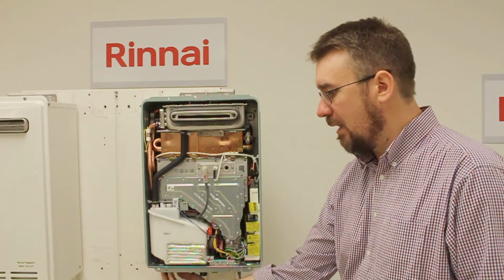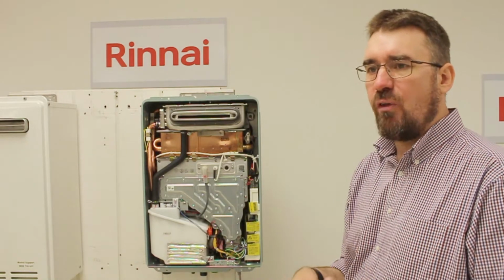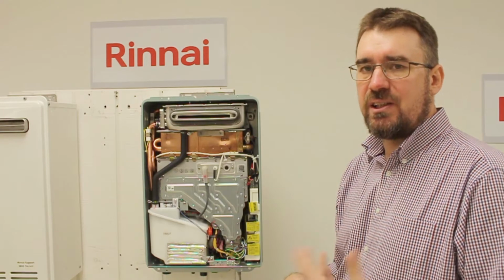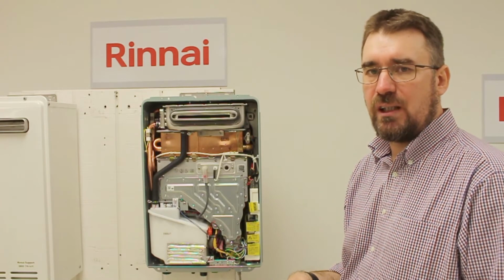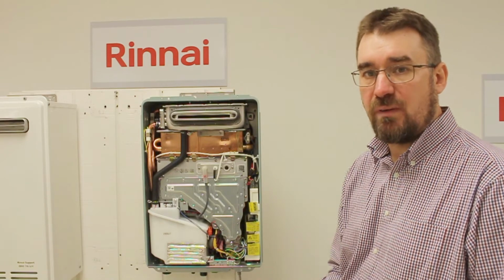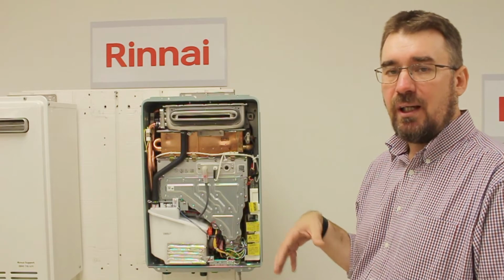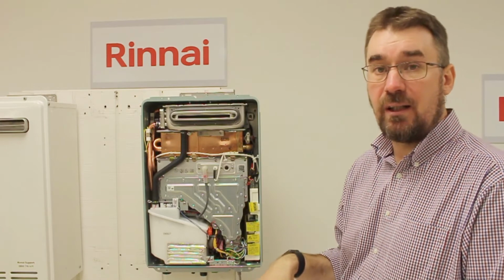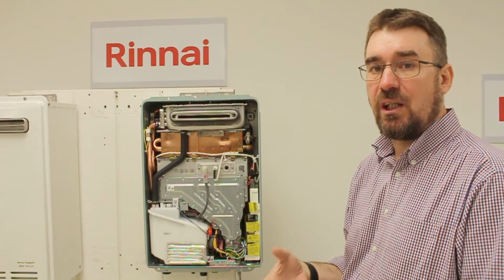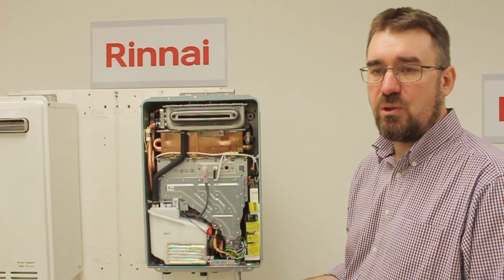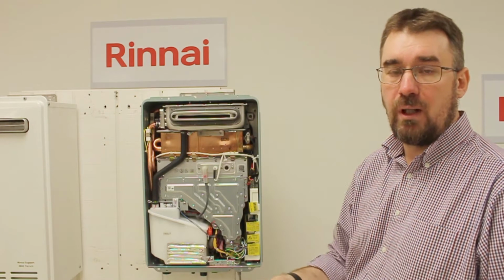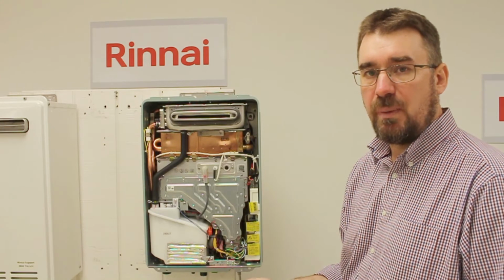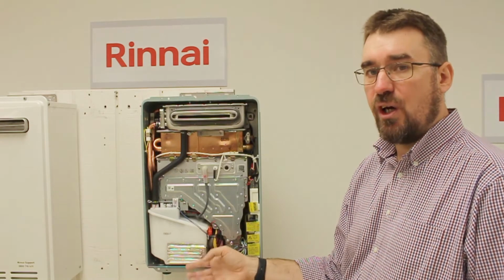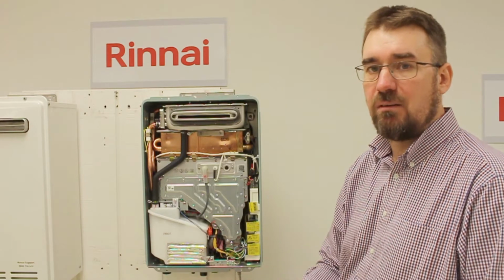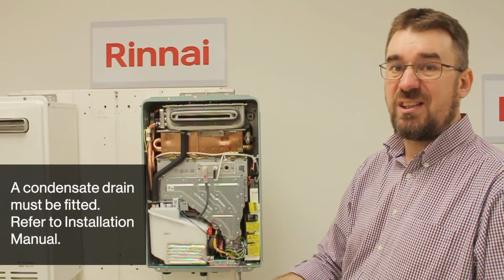So now the condensate drains out the condensate drain and away, and we've got a far less acidic concentration of condensate coming out of the unit. When we dispose of that condensate, we still need to dispose of it sensibly and in the correct area. But we've not got acidic condensate, so issues with where it might go into cement, for example, or other things more prone to being eaten away by acidity, are less of a concern. We still do need to drain it away effectively. All that information is in 5601. You just need to follow that and the instructions we supply with the unit.